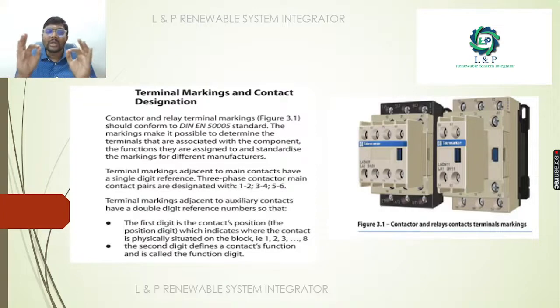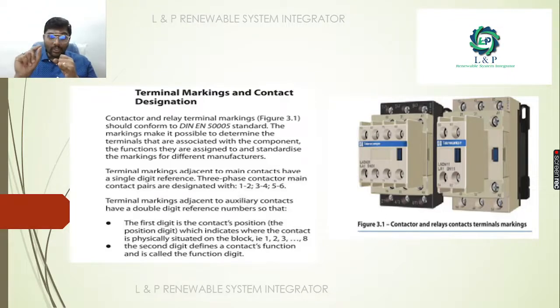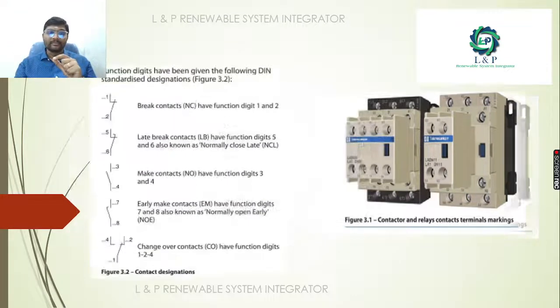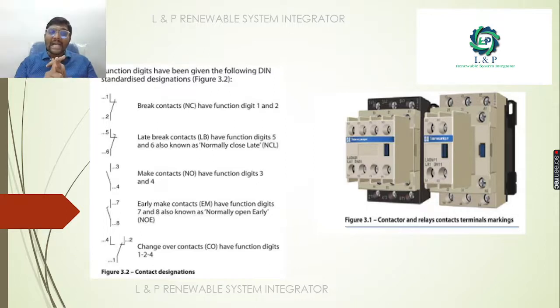Terminal marking and contact designation: this is an example of a contactor and relay terminal marking. The first digit is the contact's position, indicating where the contact is physically situated — it can be 1 through 8. The second digit defines the contact function. For a normally closed break contact, the function digits are 1 and 2. For a late break contact, the function digits are 5 and 6.